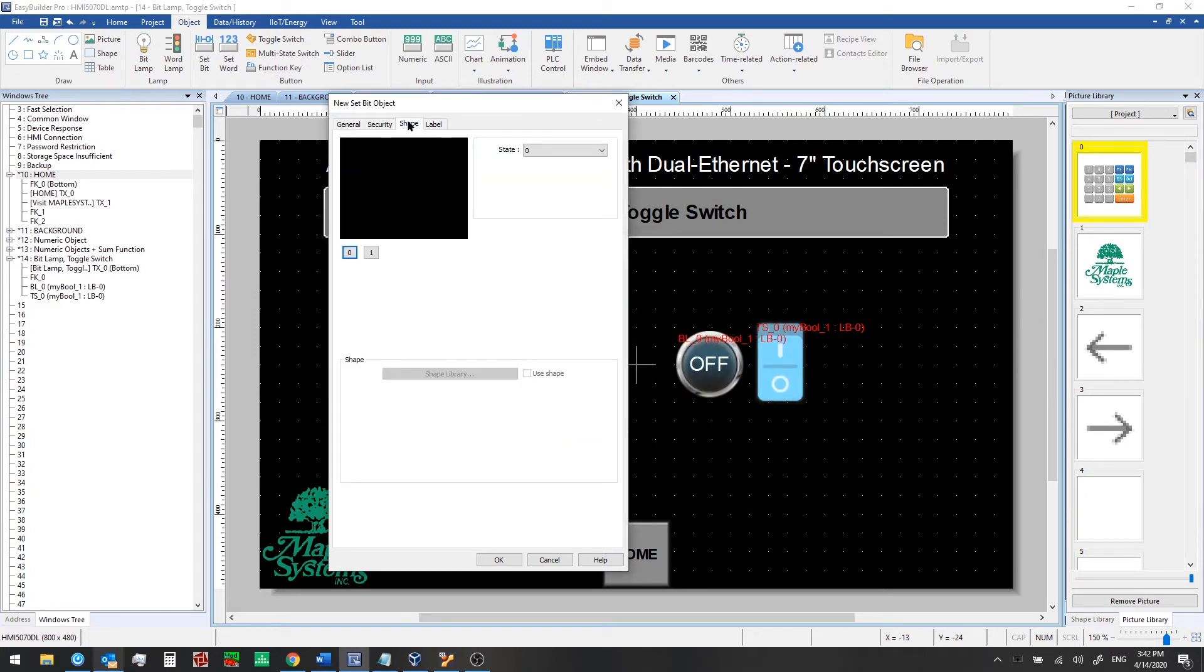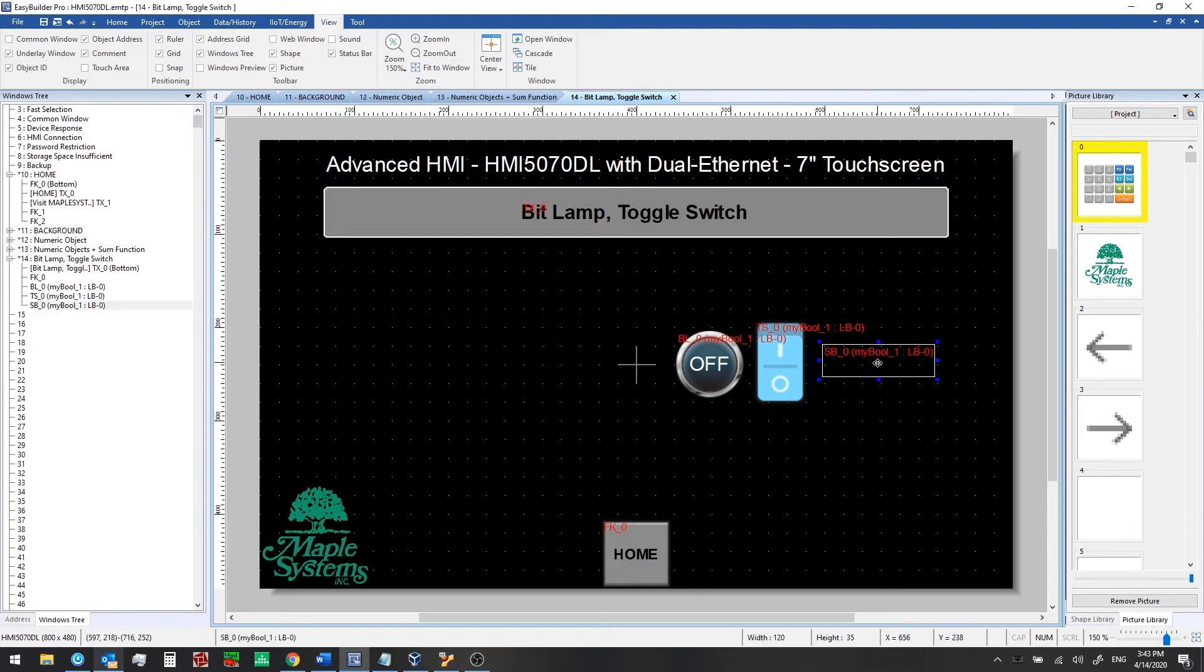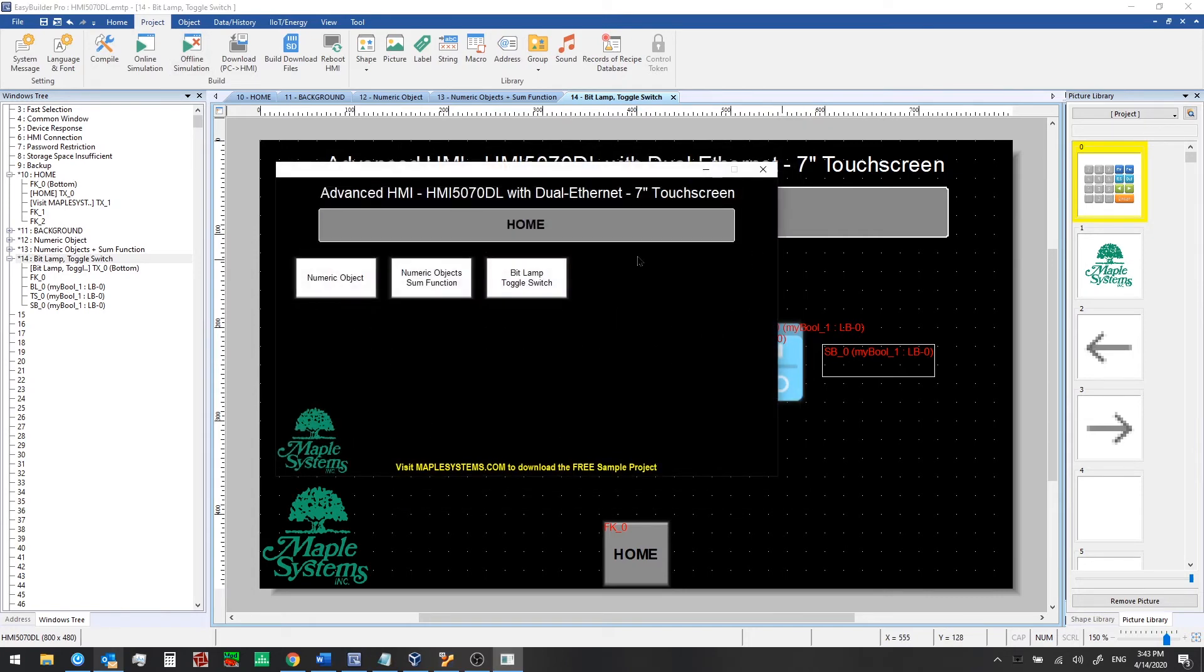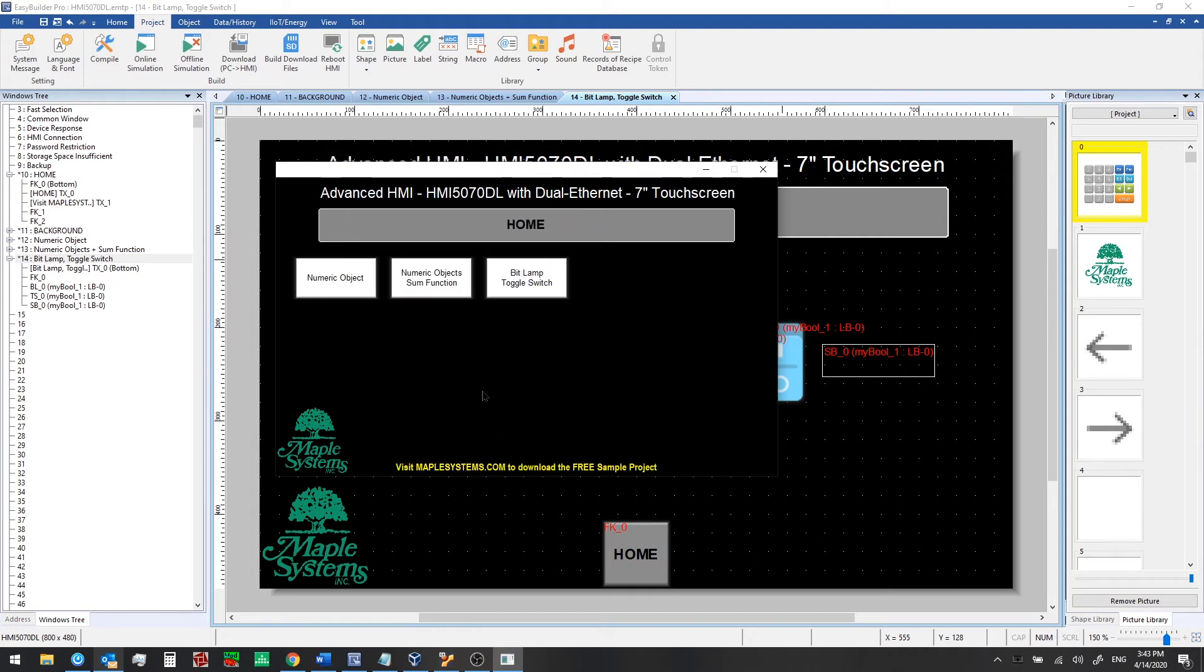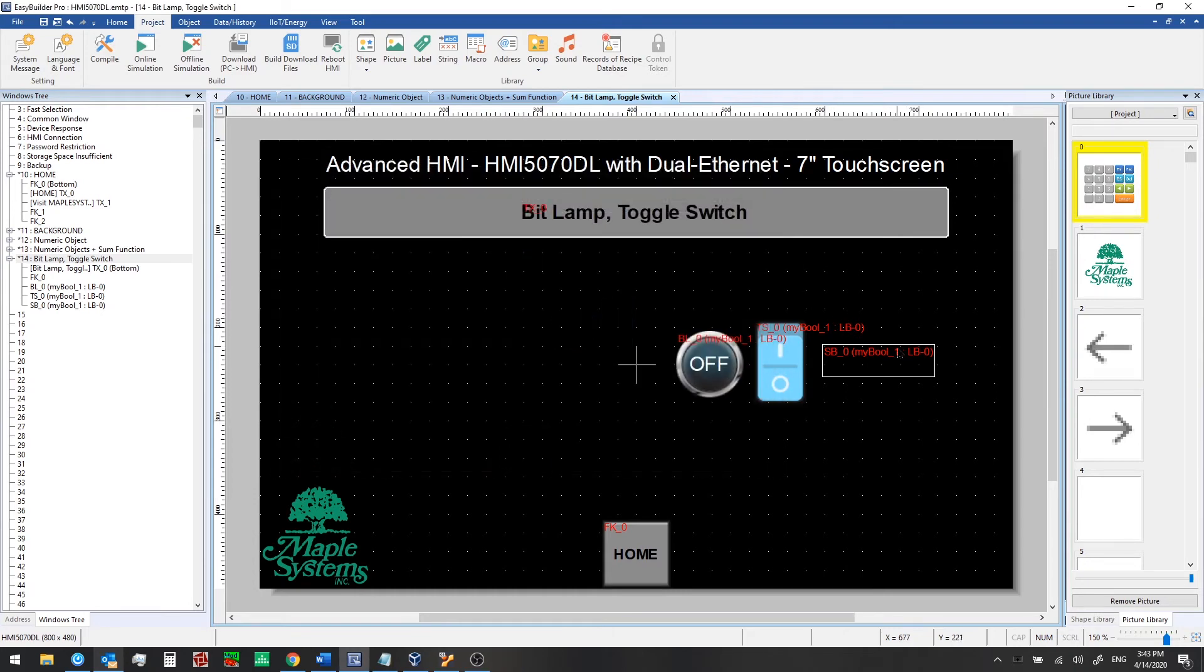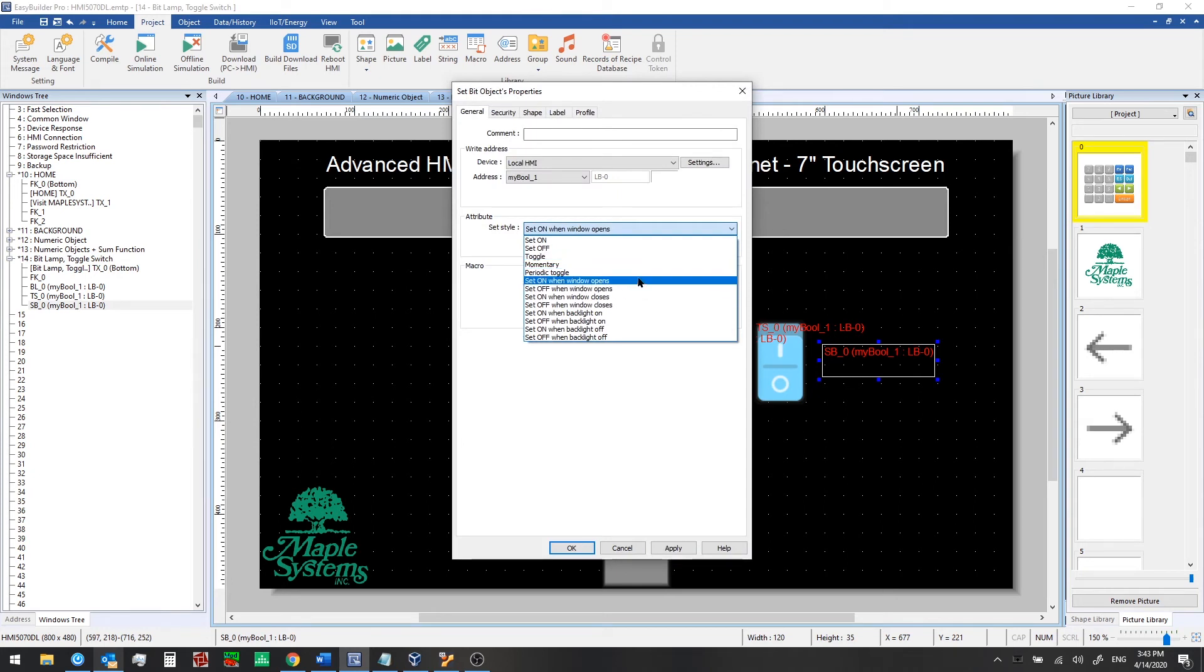Okay, so there's no shape. We'll click OK and add that. You just see the outline there and the object address and object ID. There's no picture or anything. So we'll go ahead and run the offline simulation again. And this time when we navigate to the window we should expect to see it on. And it is. There we go. We can still turn it off and on again. If we go back to home and then come back to this window one more time, it'll be on one more time. So that set bit functions in that way. Set on when window opens. We can also set off when window opens, do the same types of actions when it closes.